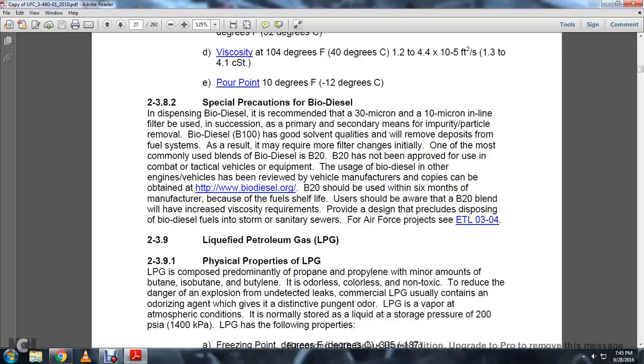2382 special precautions of the biodiesel. In dispensing biodiesel, it is recommended that a 30 micron and 10 micron in-line filter be used in succession, primary or secondary means, to remove impurity particles. B100 has good solvent qualities and will remove deposits from the fuel system. As a result, it may require filter changes initially.